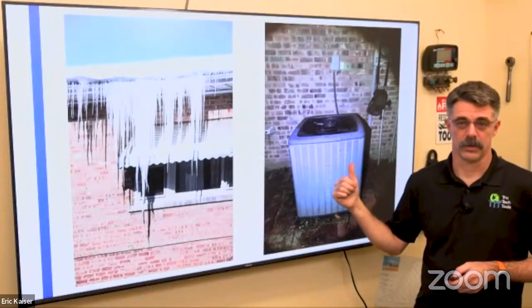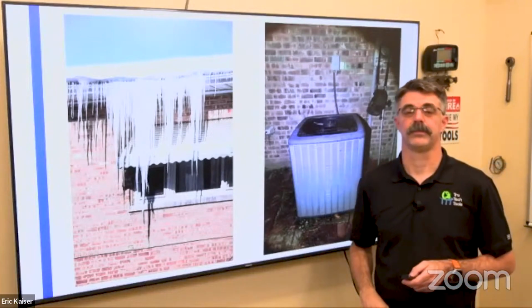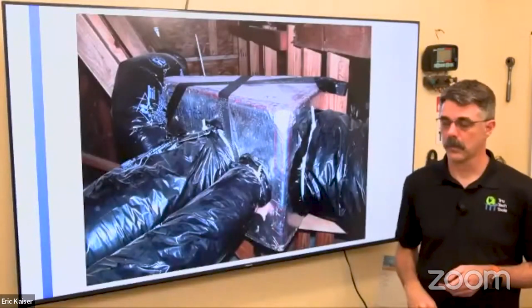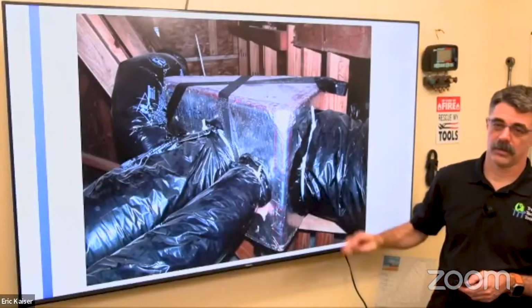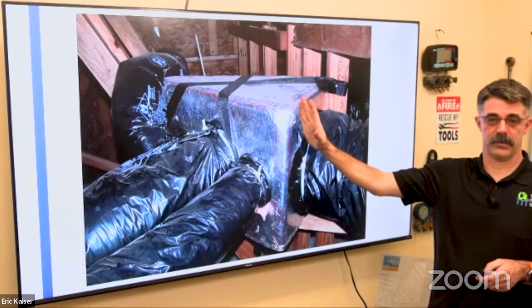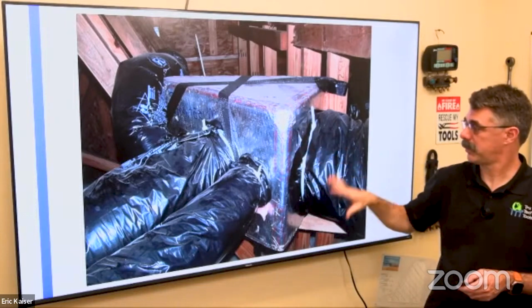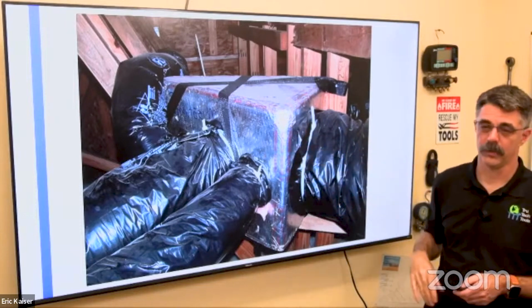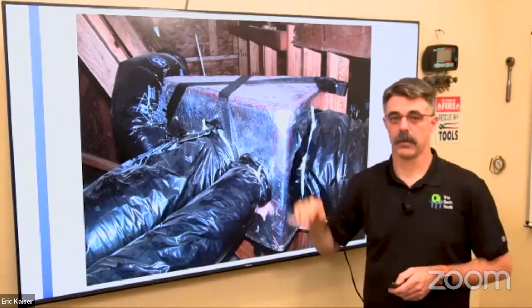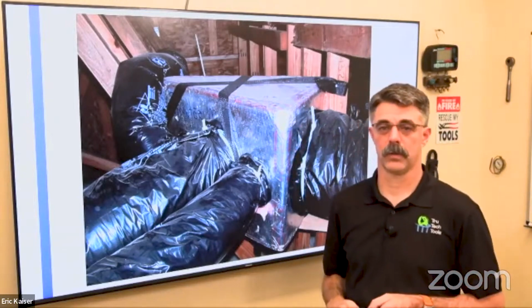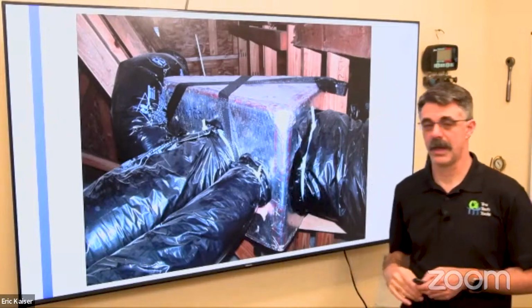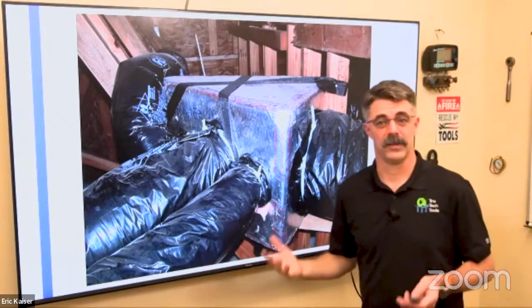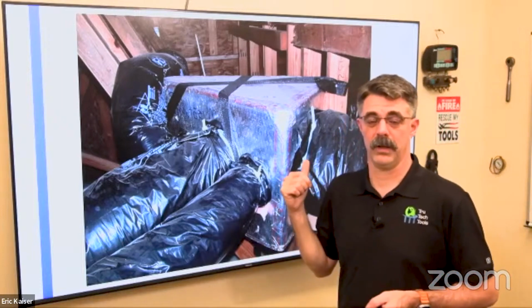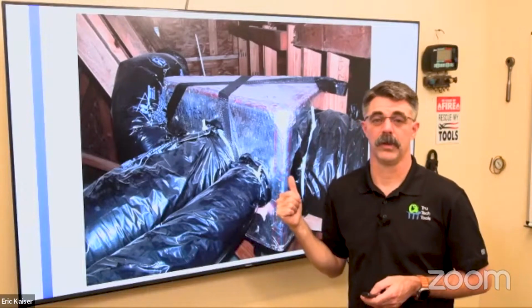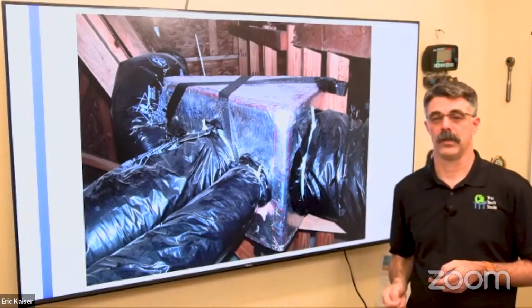But just a note of caution, right? It happens. All right. Make sure that the ductwork is up to par, that everything's insulated and well sealed. Maybe take out the Bermuda Triangle of ductwork here if you see that. But again, you can test it, see how things are working. If there are problems, recommend getting them replaced to the customer.